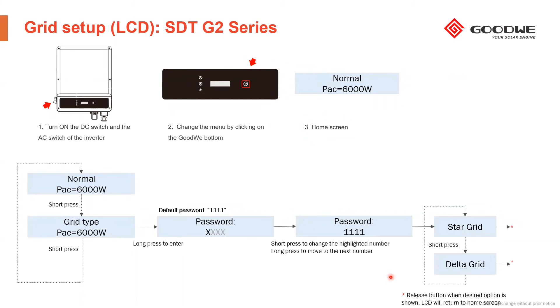So usually it's a star, but depending on the market, the grid we are working with, the facility, we need to confirm if the inverter will work in a star grid or a delta grid. That is basically all we need to do in the grid setup. As you can see, it's very, very simple.